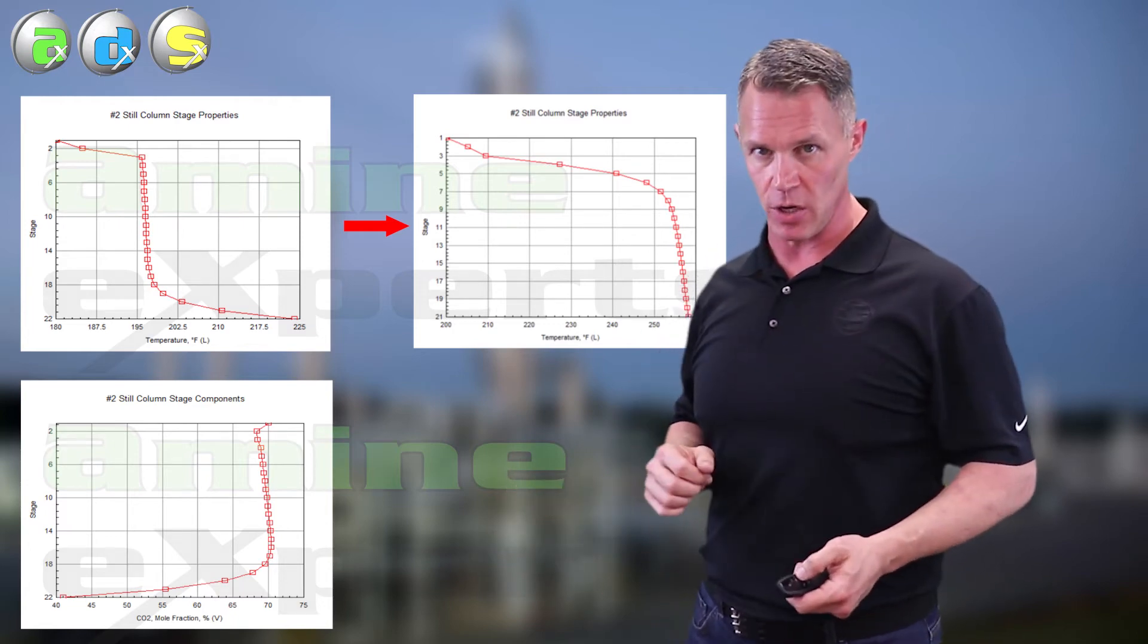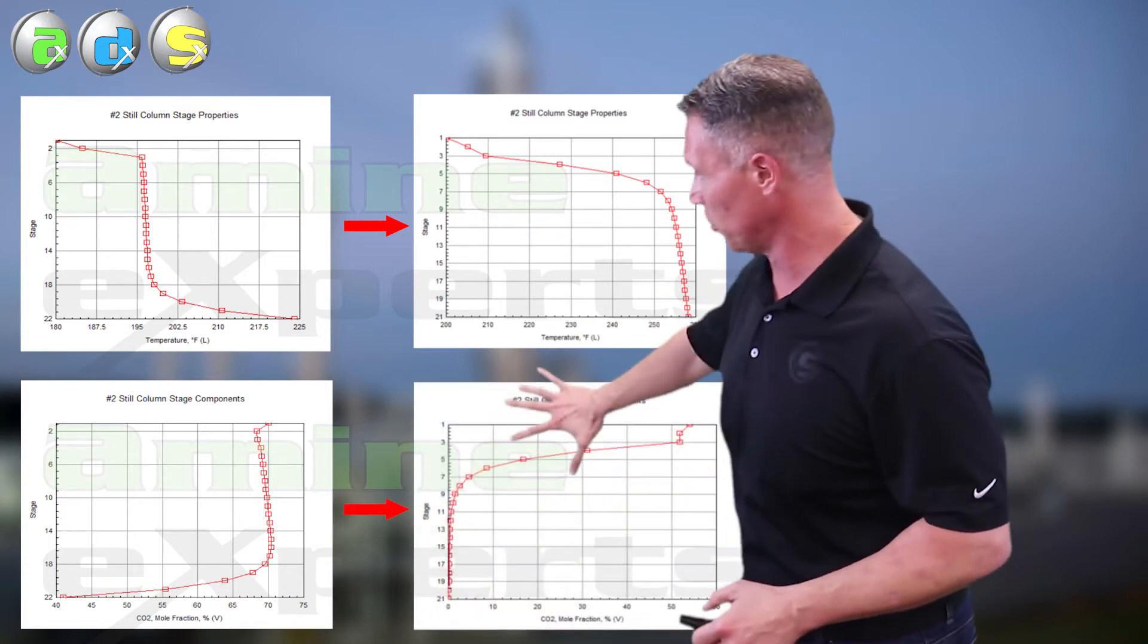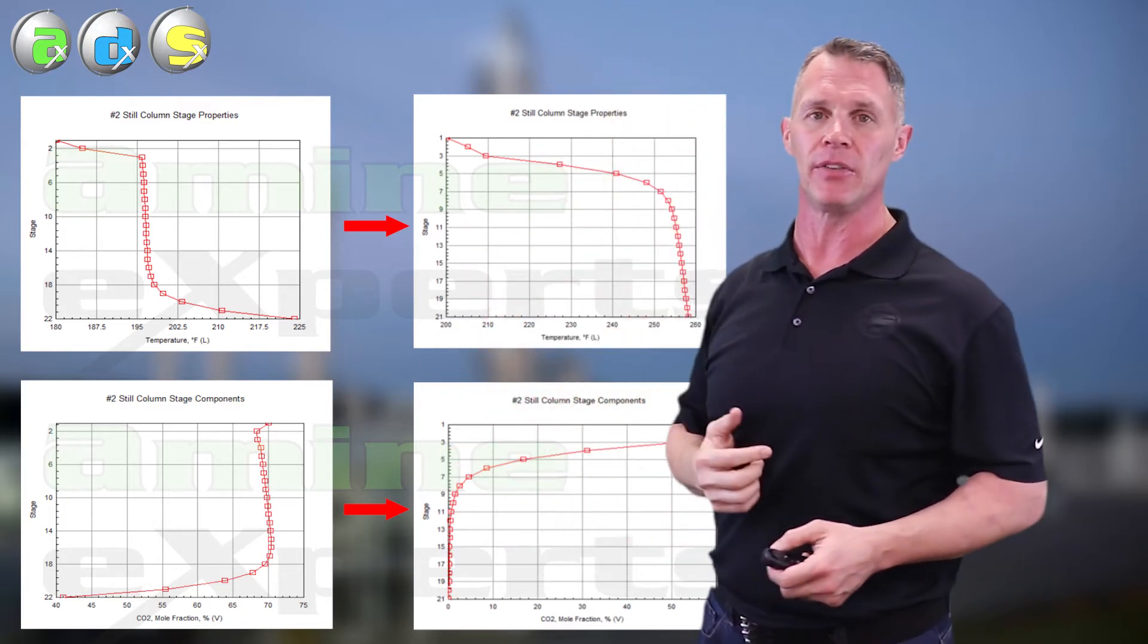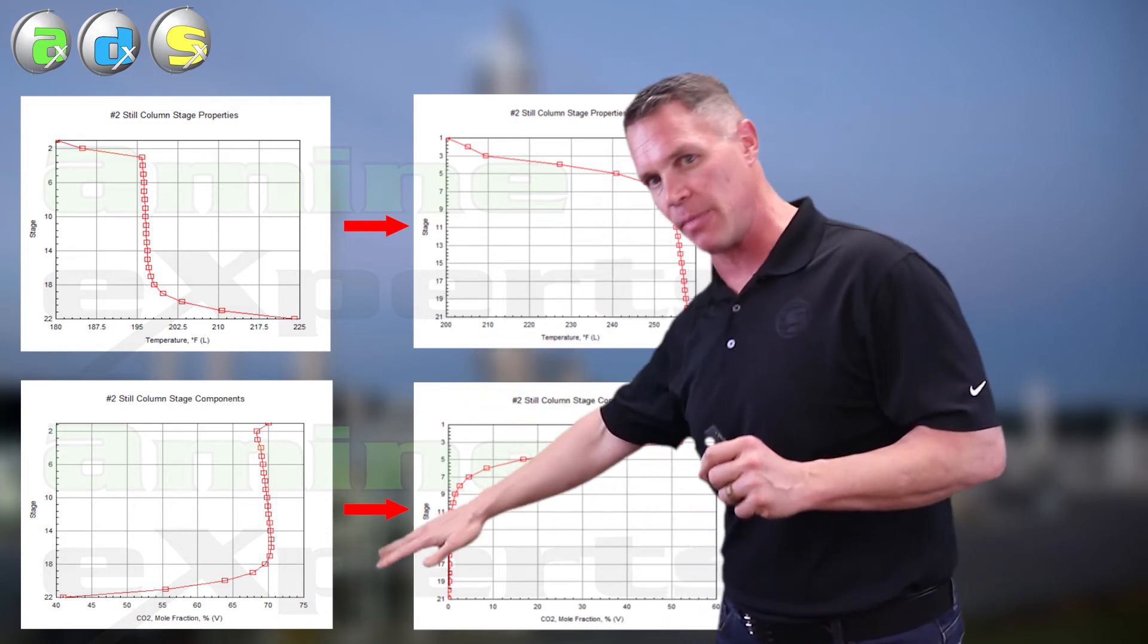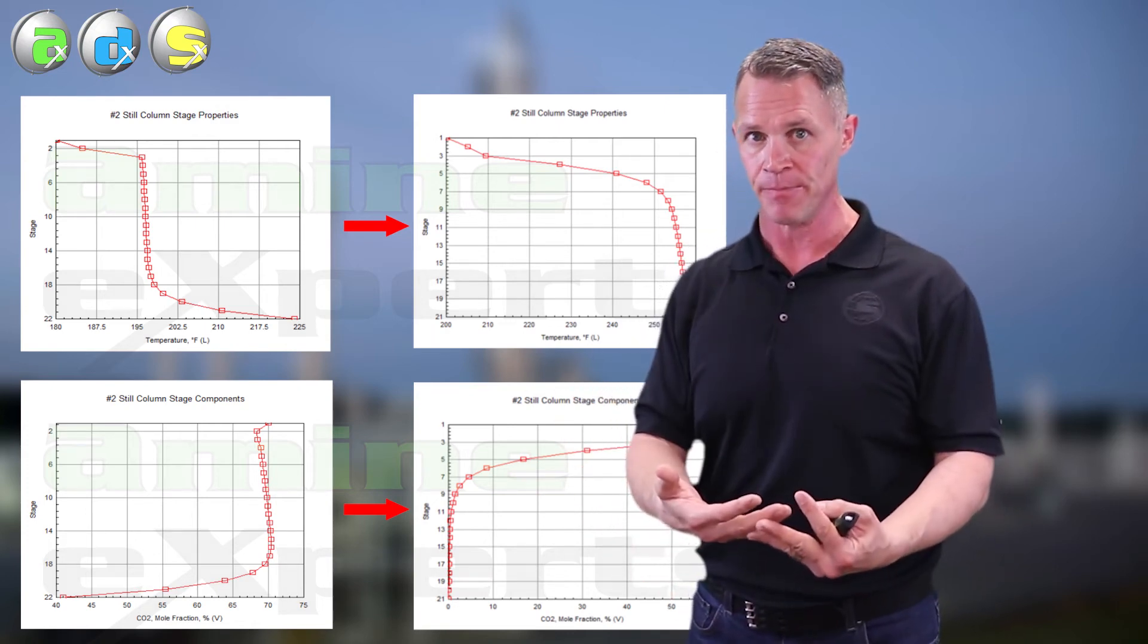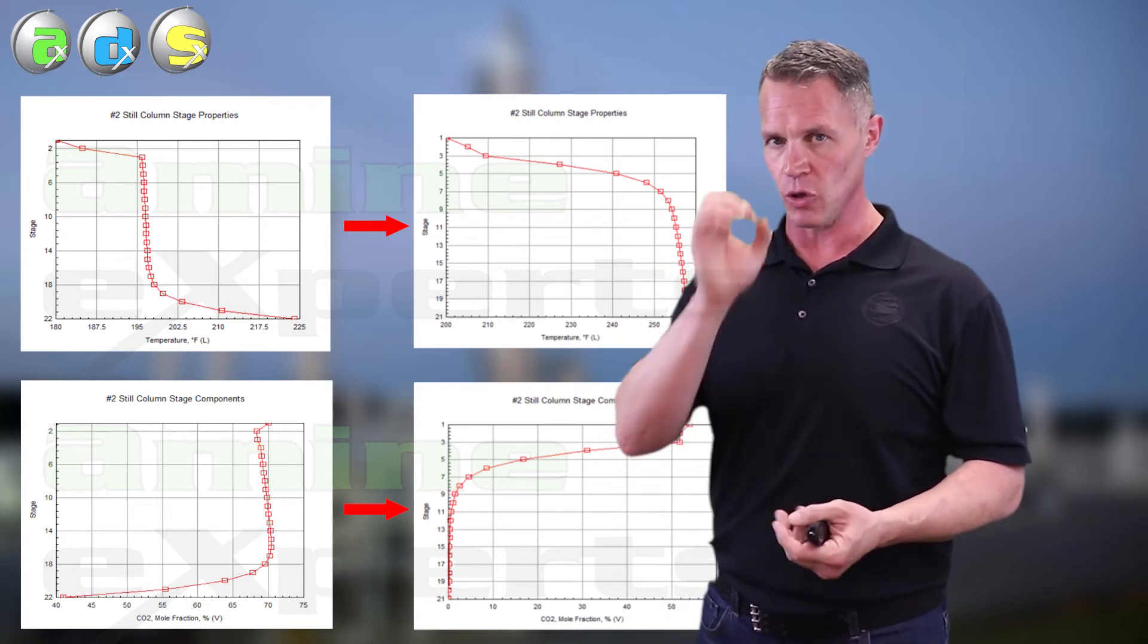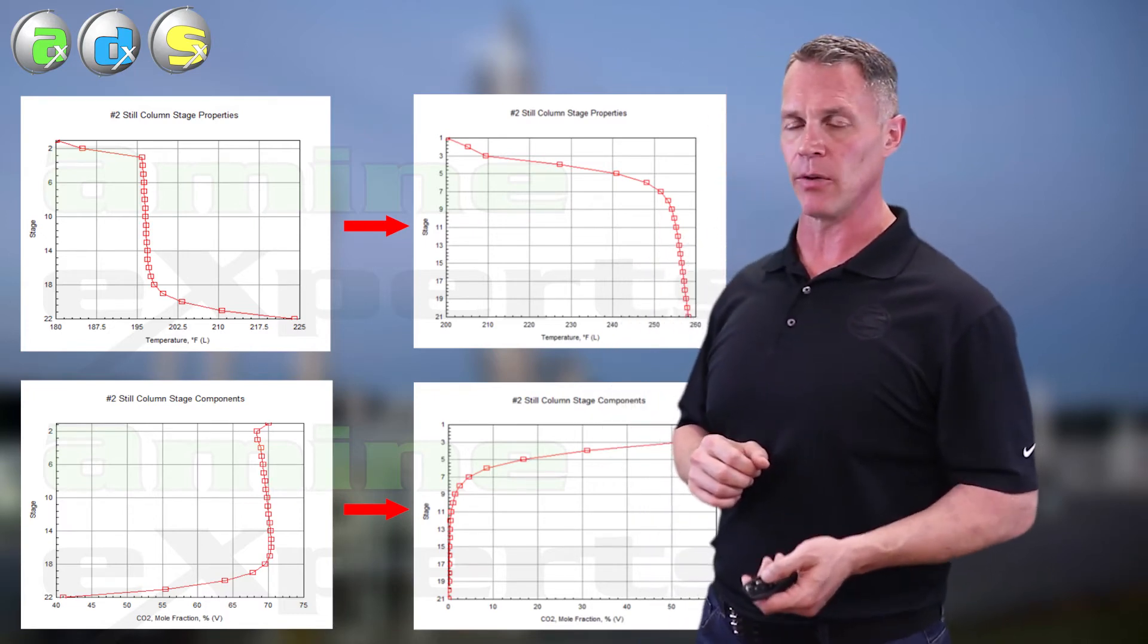What does that do to our CO2 profile? It does very good things to it. If you look down here, the corresponding CO2 removal profile, the amine came in, the CO2 very quickly dropped because we're flashing it up into the vapor space and we're getting rid of it. And ultimately, what happens is by the time that amine feeds the reboiler, there are no CO2 left. It's just lean amine. When we don't have CO2 entering the reboiler, we don't have anything wanting to corrode the reboiler either. So proper regeneration is fundamental in a CO2 only plant regeneration.